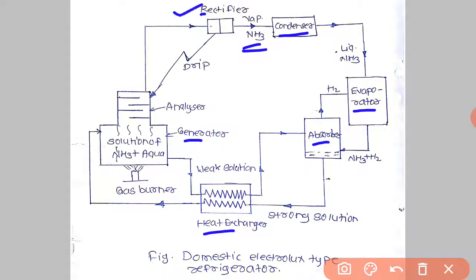So the function of the rectifier is to remove water vapors. So dry ammonia vapors are supplied to the condenser. Totally dry ammonia vapors will be supplied to the condenser. If the water vapors are not removed, they will enter the evaporator, and they will freeze and choke the system. So it is necessary to remove water vapor and we have to pass pure ammonia vapors to the condenser.